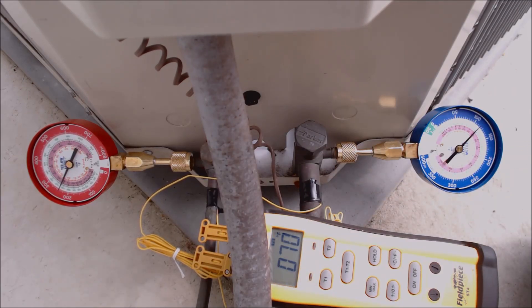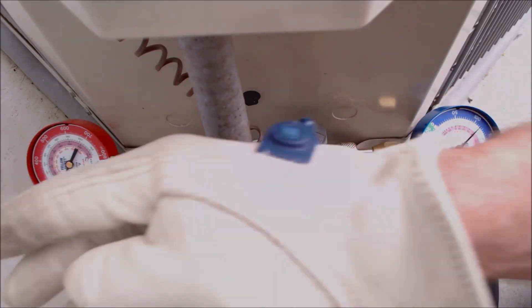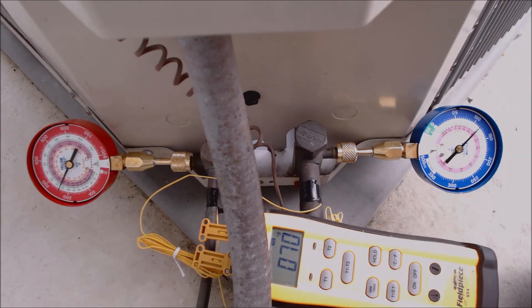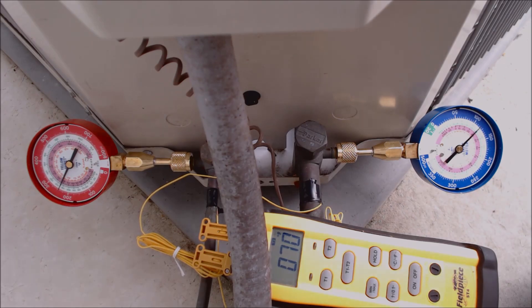I went inside and confirmed we have somewhere between 18 to 21 degrees delta-T across the evaporator coil — that's the temperature decrease between the return air and supply air inside the building. As the system runs, both the suction pressure and discharge pressure are going to fall, due to the indoor wet bulb temperature lowering as the system doesn't have to work as hard. Now I'm going to go ahead and disconnect everything.